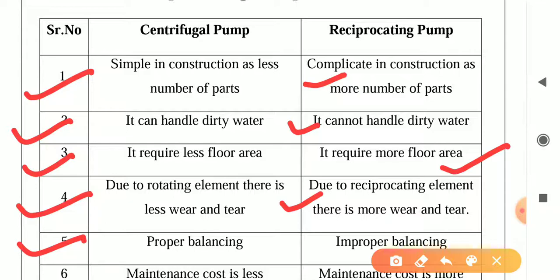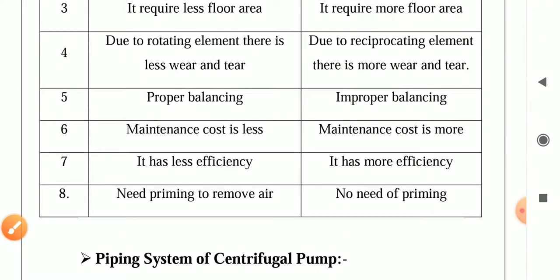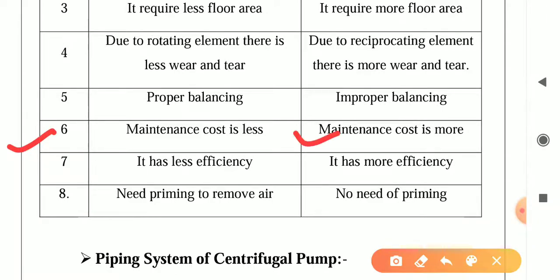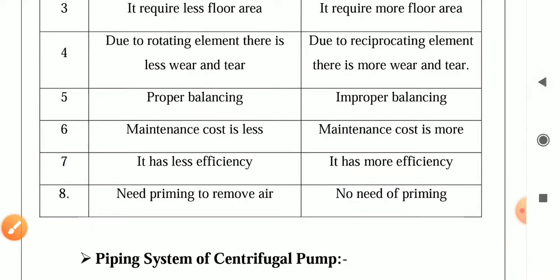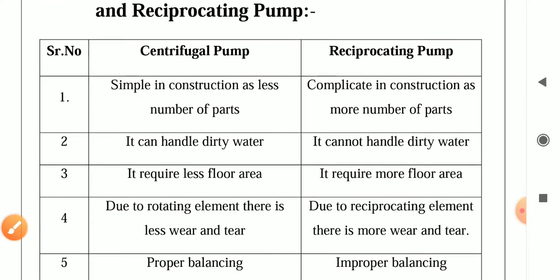In reciprocating pump, there is improper balancing. Maintenance cost of centrifugal pump is less; maintenance cost of reciprocating pump is more. Centrifugal pump has less efficiency; reciprocating pump has more efficiency. Centrifugal pump needs priming to remove air; reciprocating pump has no need of priming. These are the points differentiating centrifugal pump and reciprocating pump, and this is also asked for four marks.